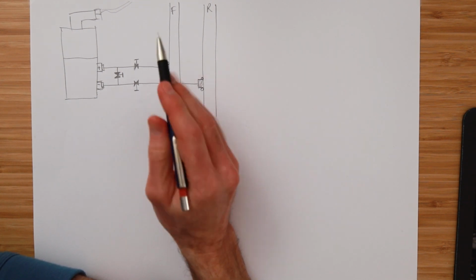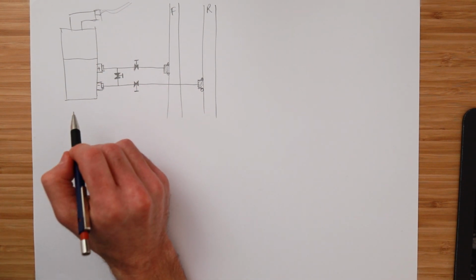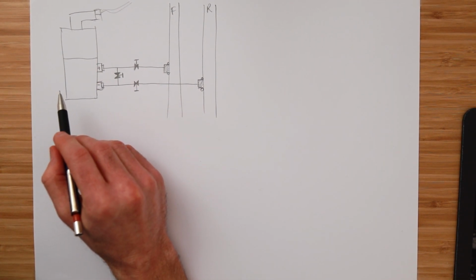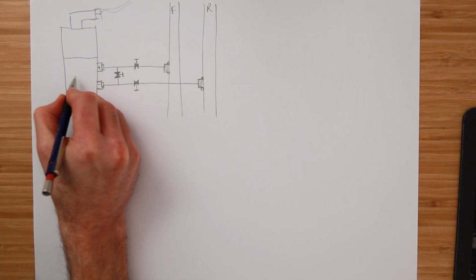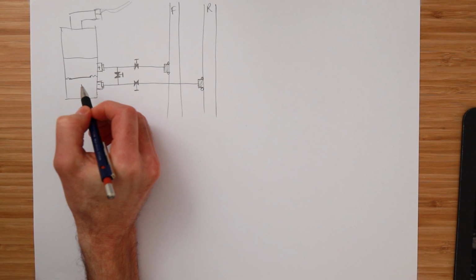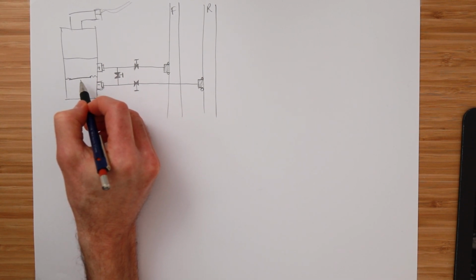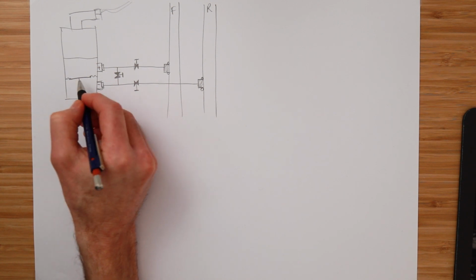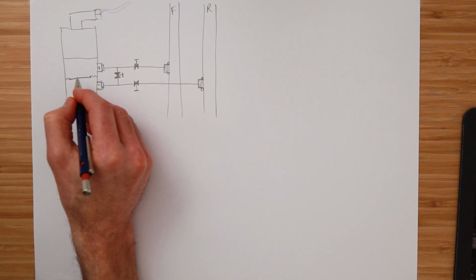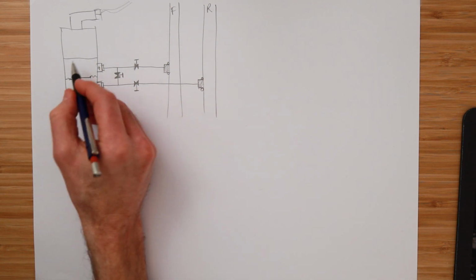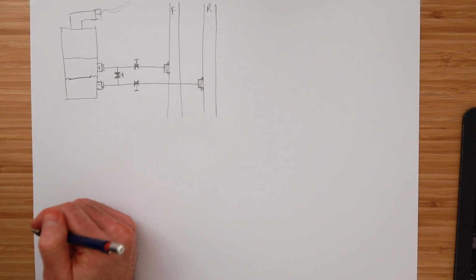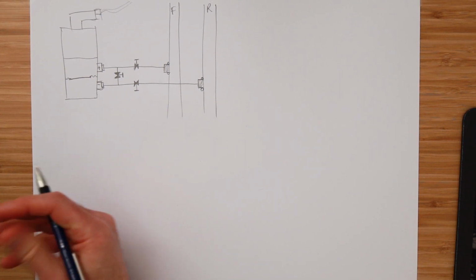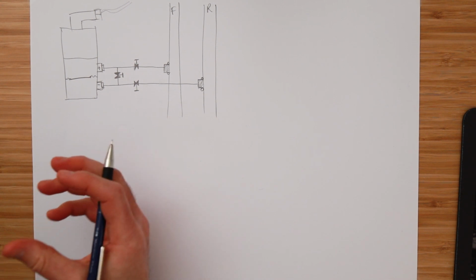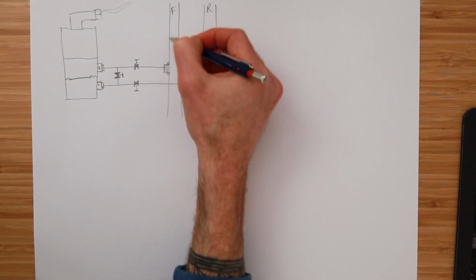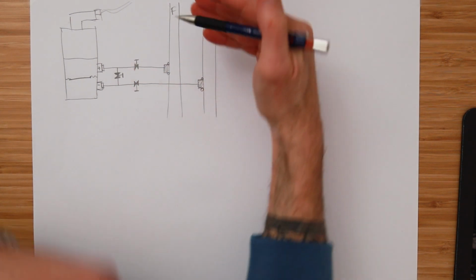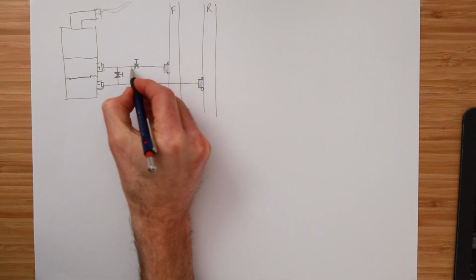So the problem we have, actually before we get to the problem, let me explain this. In my opinion, most pressure sensors work with a diaphragm. So inside here, there's a diaphragm. I'm not saying they all do this, I think they mostly do. There's probably other types of sensing arrangement, but the ones that I think we have the most of is this diaphragm method. And what happens is, say this transmitter is sitting in the basement and you've got 30 floors of commercial office above you. There's a lot of static pressure in that pipe. The static head, all the water that sits in this pipe, there's a pressure that sits on the flow and return on the whole building. So that pressure sits in here.